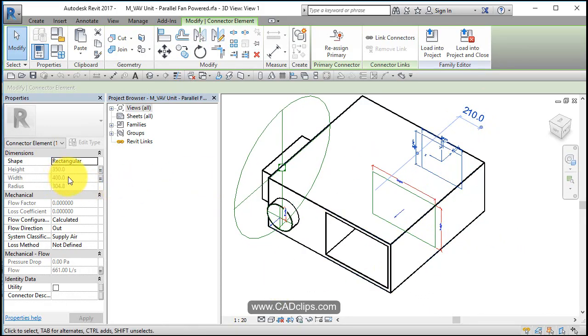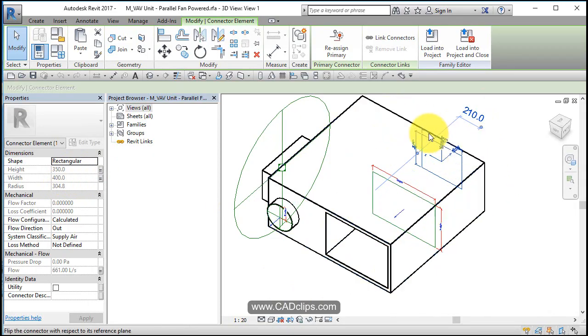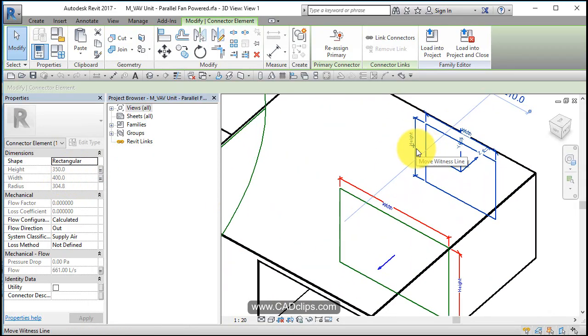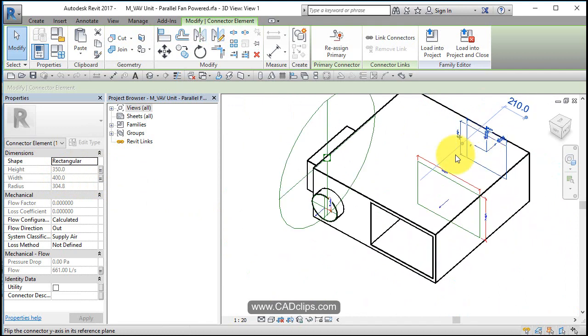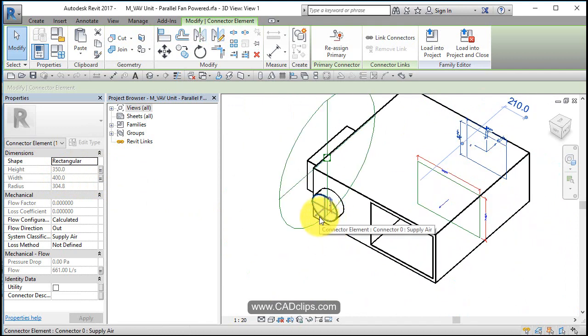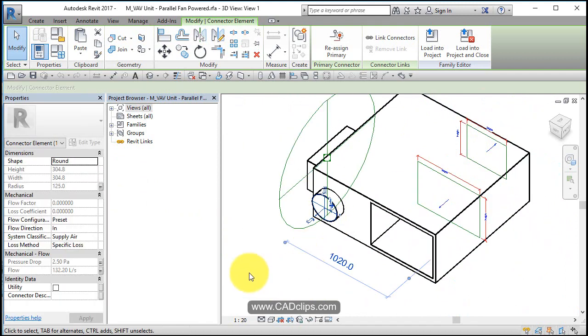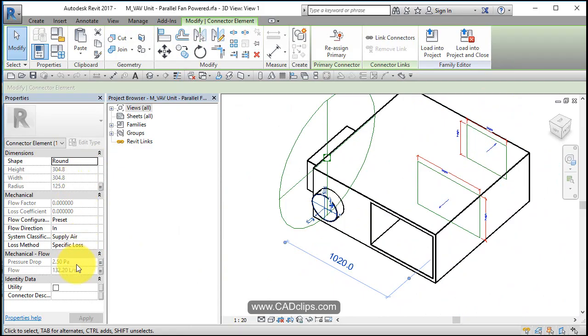So this is outbound supply air from this piece of mechanical equipment and it is set to be 400 by 350 in dimensions. That's the connector size of that when I tie into that piece of equipment. Now I also have another little connector over here which is also a supply air specified it is a diameter of 250 so 10 inches.